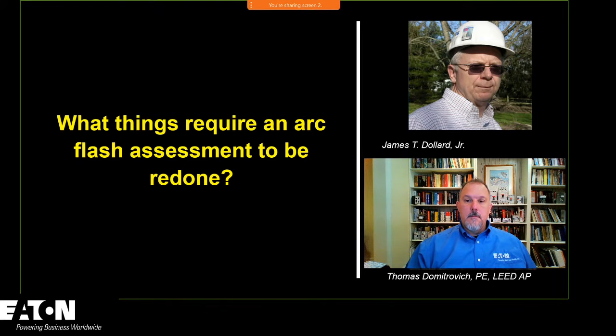But keep this in mind: that same paper found that in the same time frame, from 2003 to 2009, there were 20,033 electrical injuries, 1,573 were fatalities. What that means is one worker died for every 12.7 injuries. Wow, so it's significant, it's something we need to be aware of. We're all very interested in the arc flash hazard, but we have to keep in mind the shock hazard as well, and it represents 98% of the fatalities.